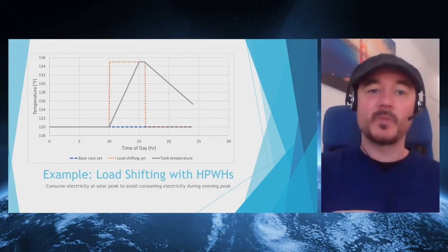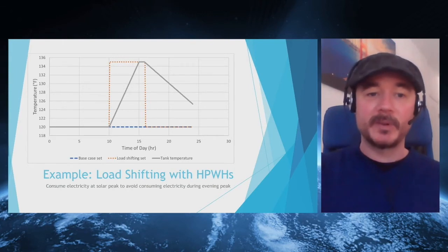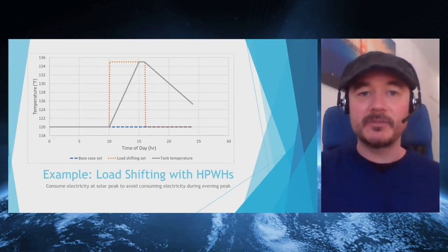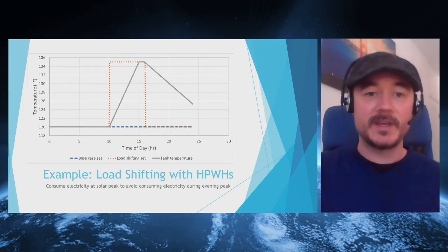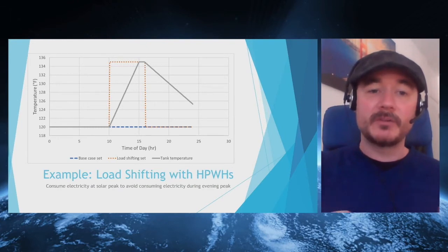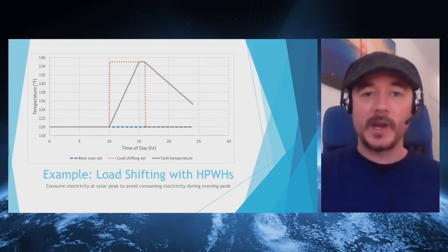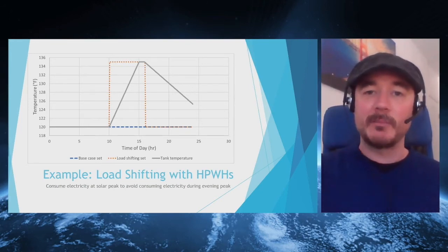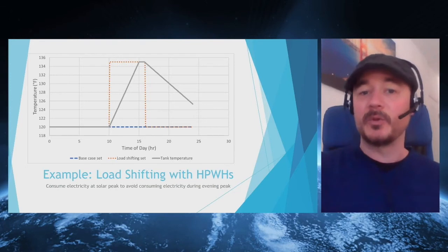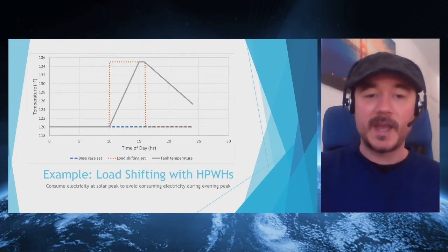At 10 a.m., when we increase the set temperature, the heat pump engages and gradually heats the water up to 135. In this example it gets there around 3 in the afternoon, then holds at 135 until 4 p.m., when we reduce the set temperature back down to 120, and the temperature gradually decreases as heat is lost to the ambient surroundings and as people use hot water and withdraw energy from the tank.